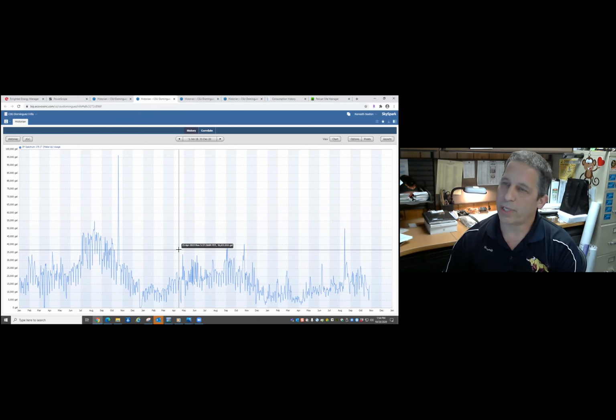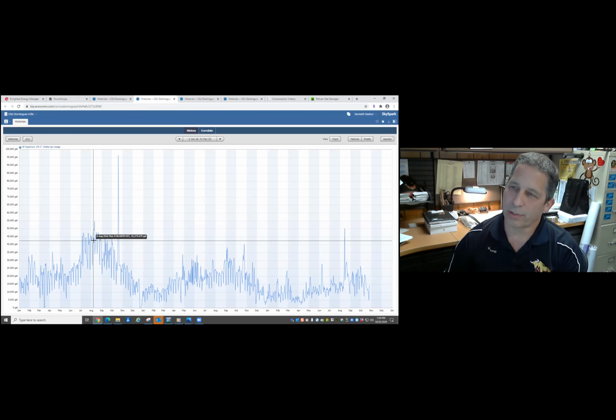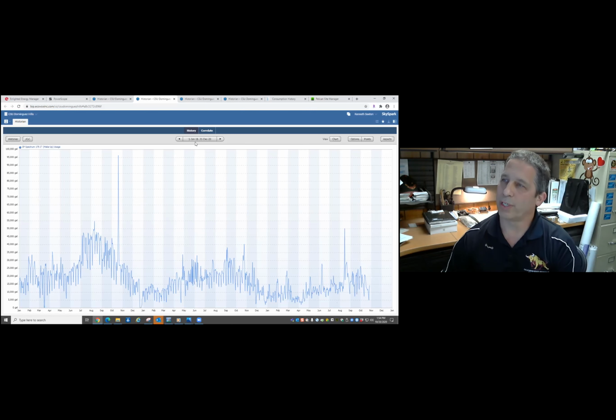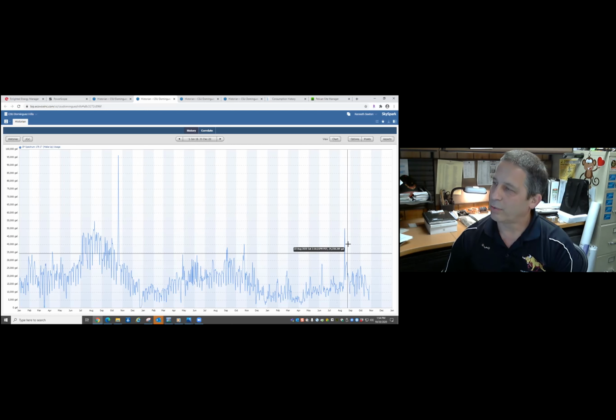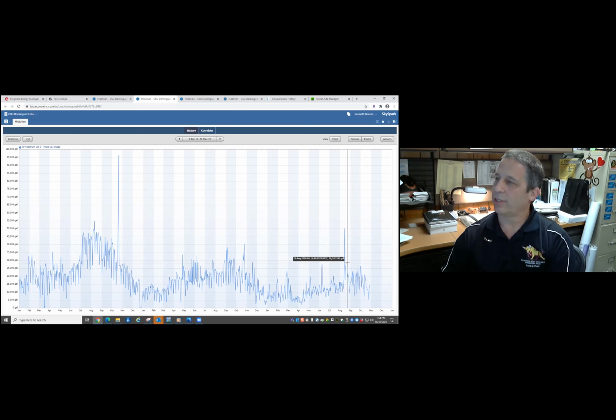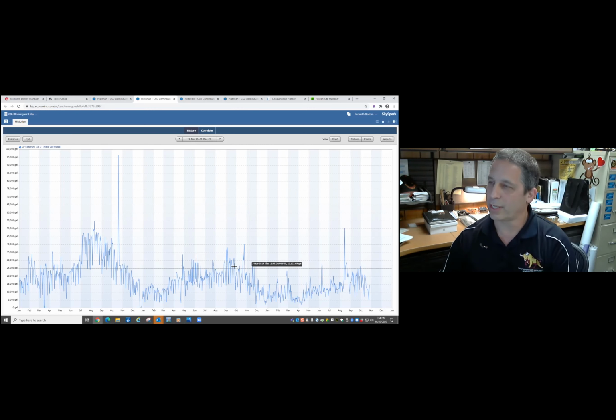This talks about our makeup water. You can see this is from a year ago, January 2018 - this is where, Brittany, you were right. We used to use like 50,000 gallons on a nice hot day - ignore this spike here, that was a problem. Now we're at 20,000 to 30,000 gallons on a hot day.